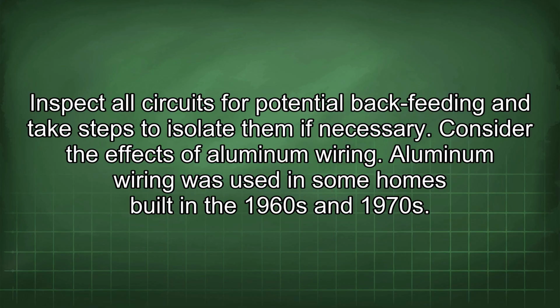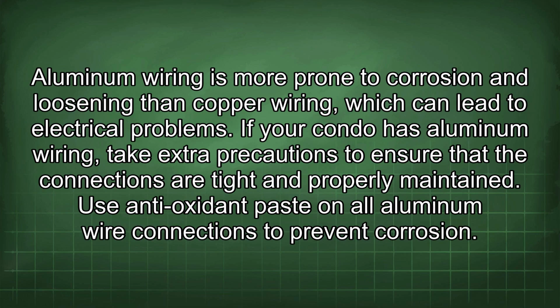Consider the effects of aluminum wiring. Aluminum wiring was used in some homes built in the 1960s and 1970s. Aluminum wiring is more prone to corrosion and loosening than copper wiring, which can lead to electrical problems. If your condo has aluminum wiring, take extra precautions to ensure that the connections are tight and properly maintained. Use antioxidant paste on all aluminum wire connections to prevent corrosion.